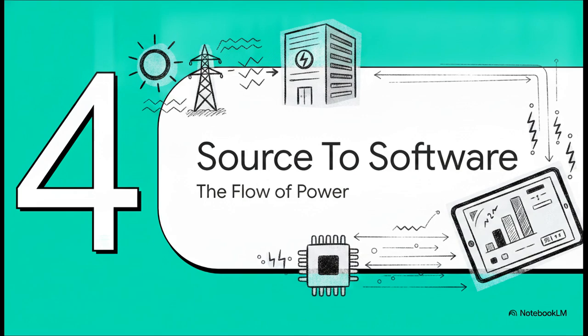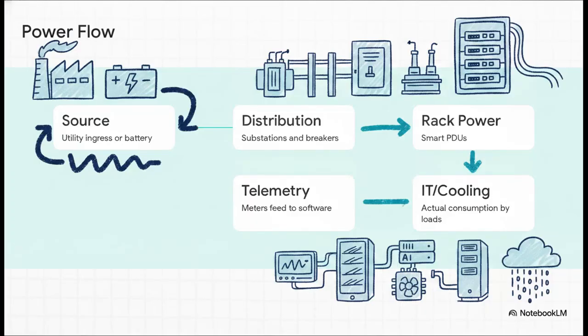Which brings us to part 4, flow, source to software. Let's see how this builds. Now that we know the physical players involved, how does that physical energy actually translate into digital data? Let's trace the sequential journey of a single watt of electricity. It starts at step 1, the power source, like our utility ingress or a battery backup. Then it moves to step 2, power distribution, through substations, breakers, and bus bars. Step 3 is rack power via smart PDUs. Step 4 is the actual consumption by the IT racks and the liquid cooling load. And finally, step 5, that physical consumption is captured by meters and turned into telemetry and software data within SuperCloud Composer. This straight line creates a single, unbroken view of power usage.